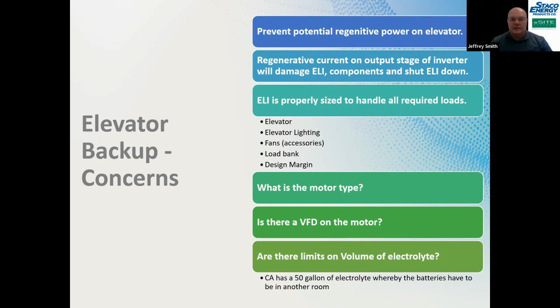And then in California, the limits of volume of electrolyte - if there's more than 50 gallons of electrolyte, or now 70 kilowatt hours of power for the battery, they want spill containment, pillows, all that type of stuff. Even though they're an absorbed glass mat battery - you could drill a hole in it, turn it over on the side, charge the heck out of it, and still maybe get a couple of drips out of it. But that's the way it goes. We do what they ask for.